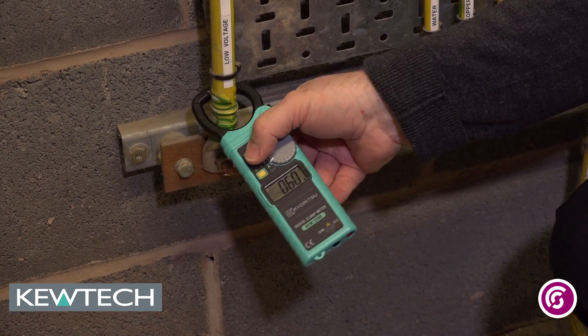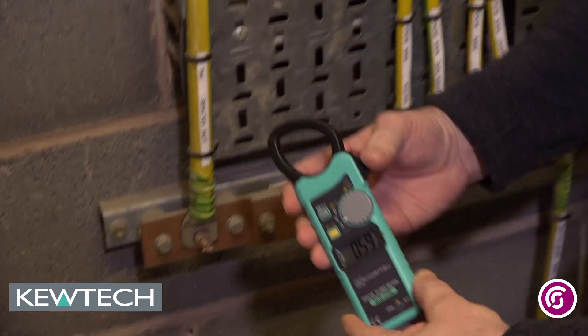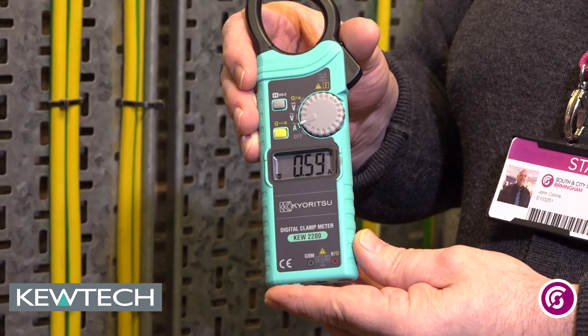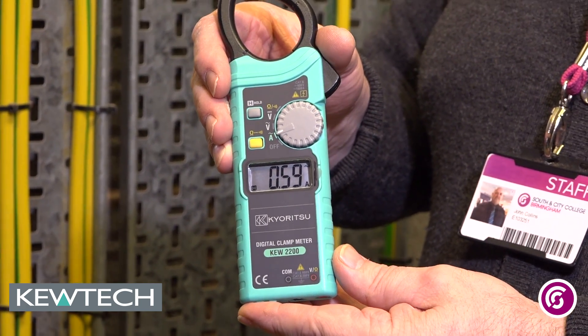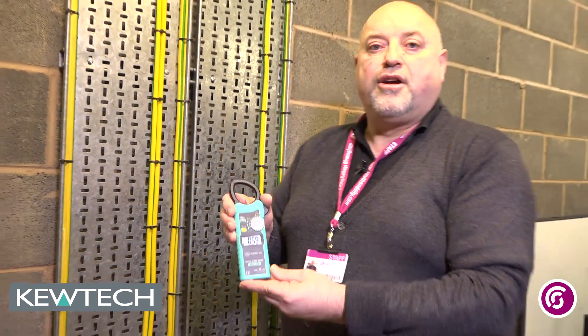Once it's stabilised, I press the hold button like so, and then I can take it off and I can see the actual leakage — which is what you'd expect anyway on installations with the amount of IT equipment and connected loads we've got leaking — and it's given me an indication of how the leakage comes. And there you have the KEW 2200.